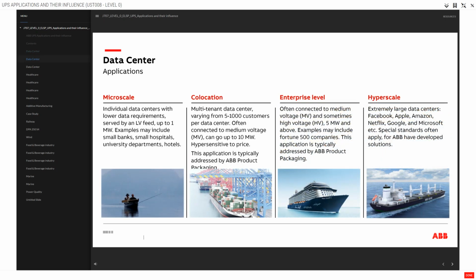Data center topologies. Microscale: individual data centers with lower data requirements, served by an LV feed, up to 1 megawatt. Examples may include small banks, small hospitals, university departments, hotels. Colocation: multi-tenant data center, varying from 5 to 1,000 customers per data center, often connected to medium voltage, MV, can go up to 10 megawatts.